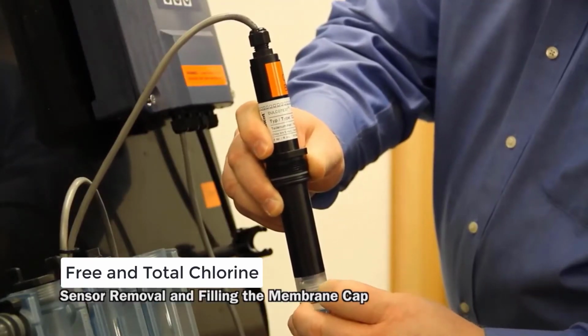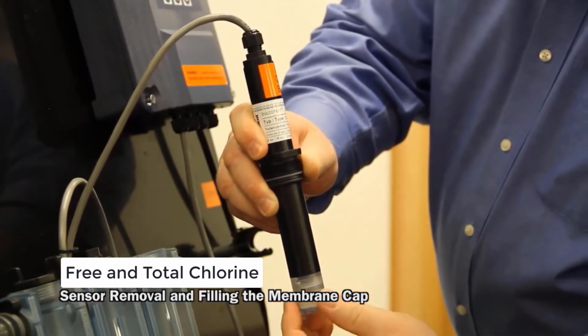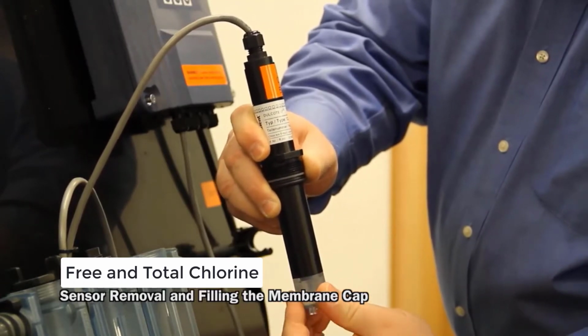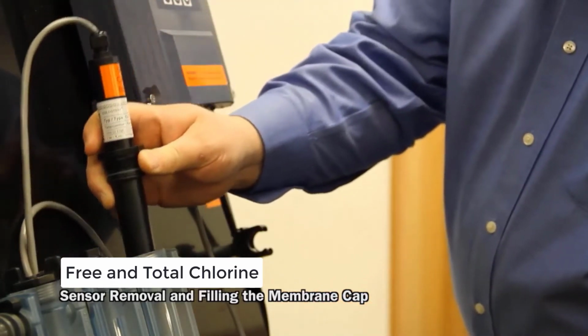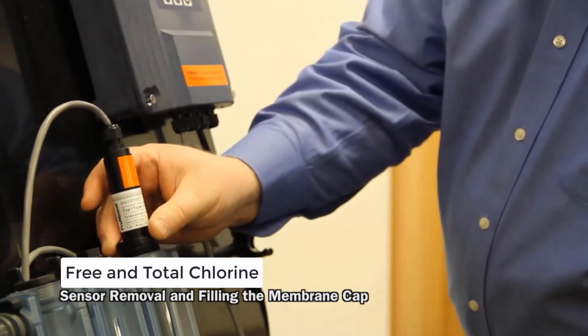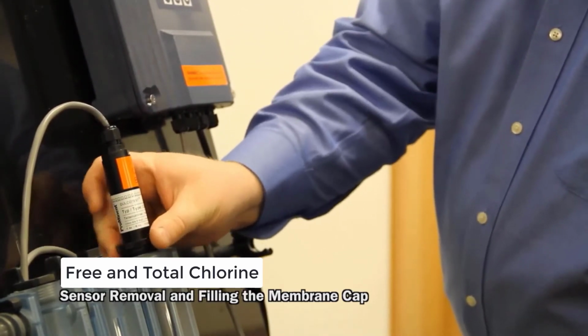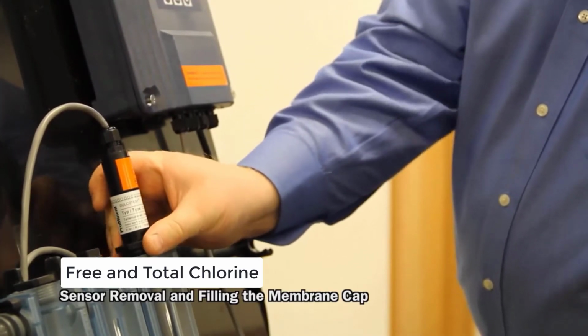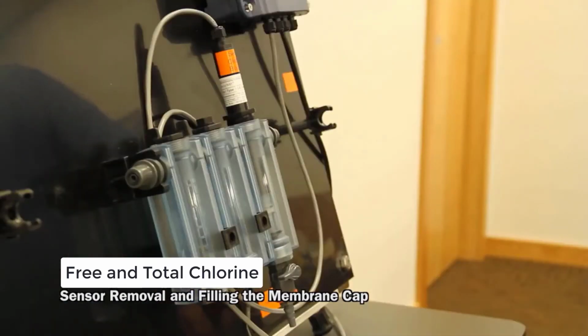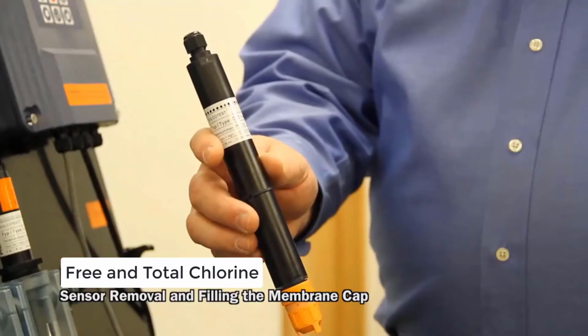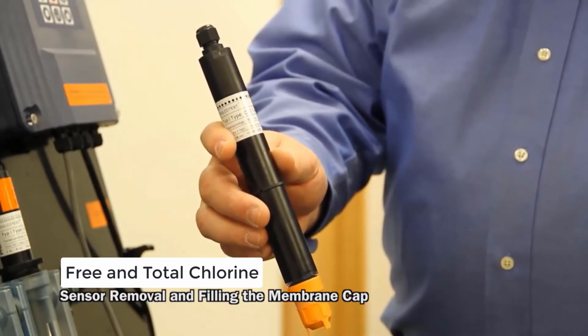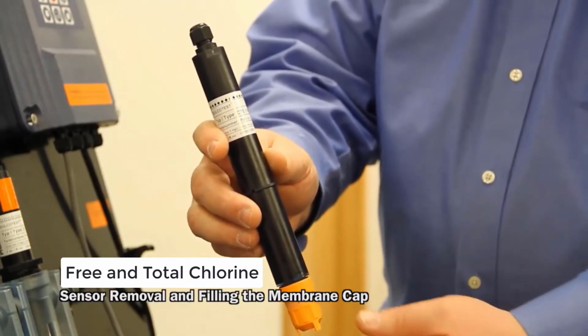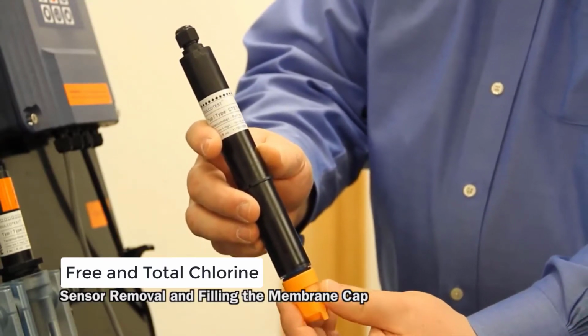Thread that cap back onto the sensor. Place the sensor back into its sample cell and tighten our compression fitting back in place. We can now start flow in the sample line after we've changed the electrolyte, or if we first installed the electrolyte. It takes several hours to get a true reading before we want to do our calibration. Some of our sensors have electrolyte that is a little bit more viscous, so to change or to add the electrolyte in that, again, we're going to remove that cap.